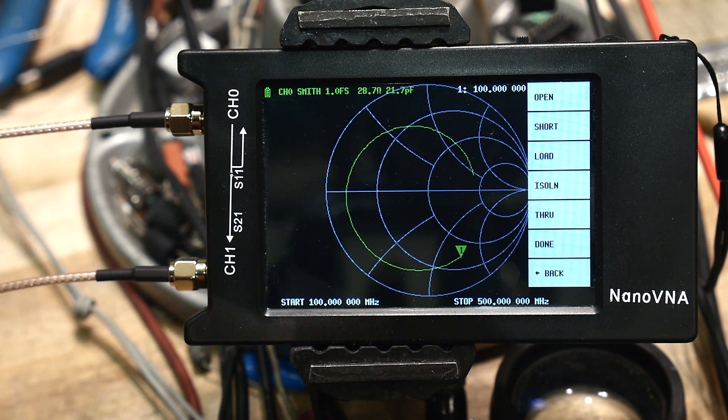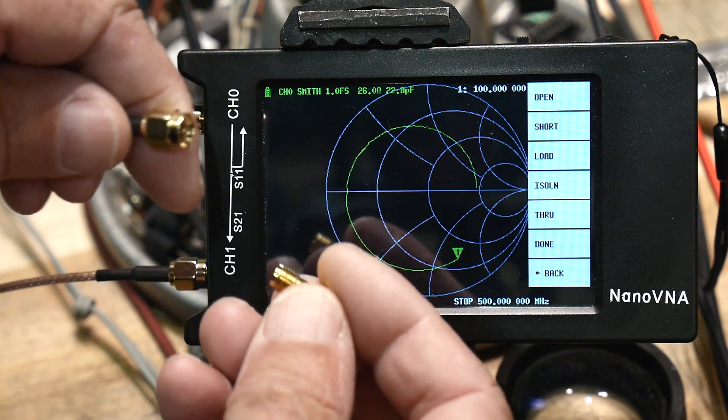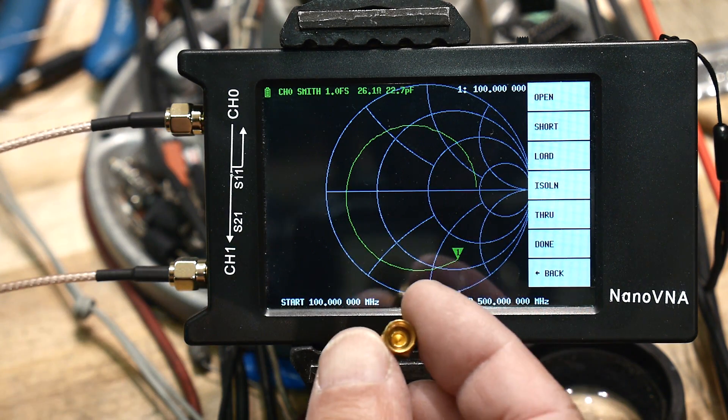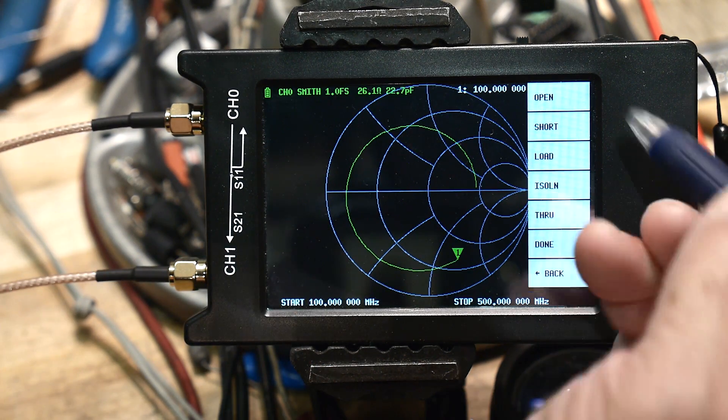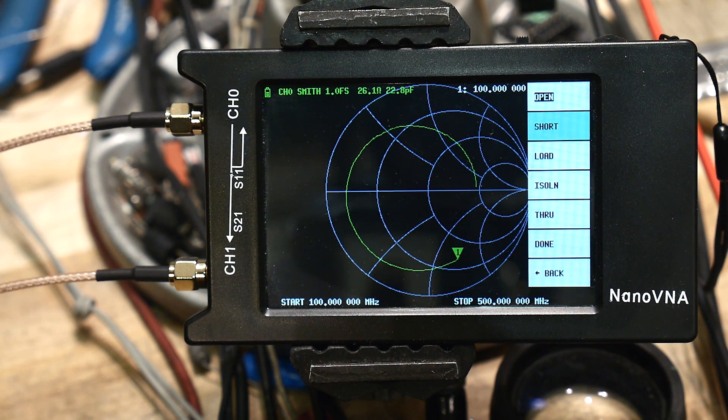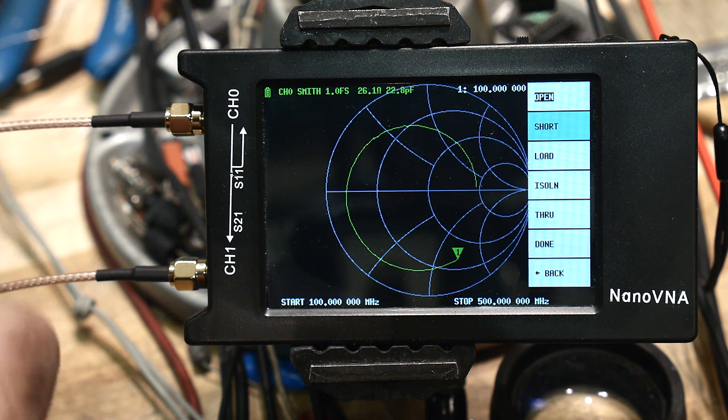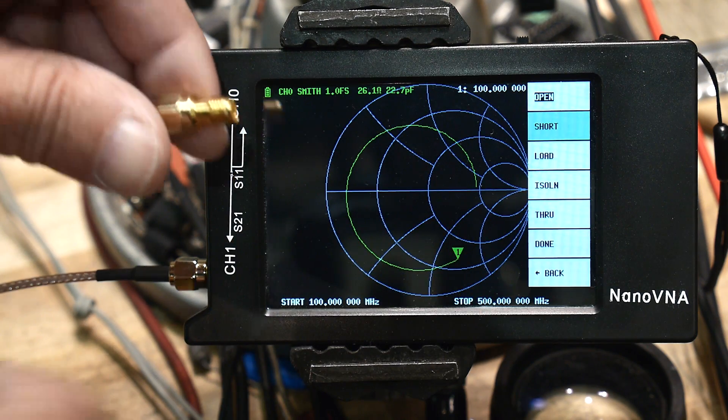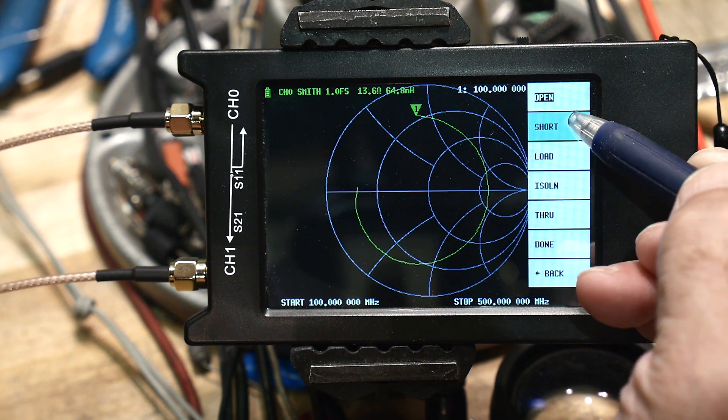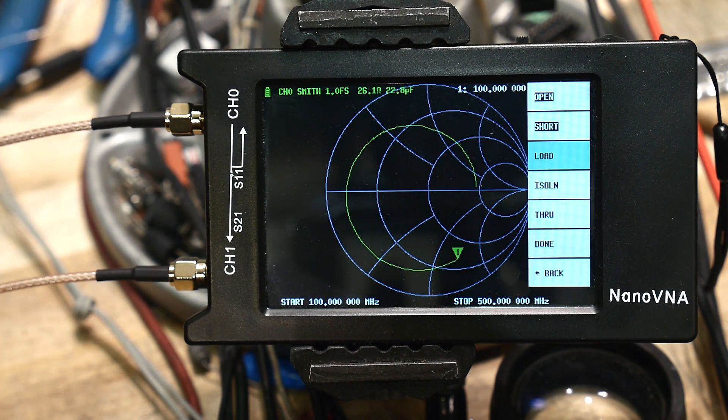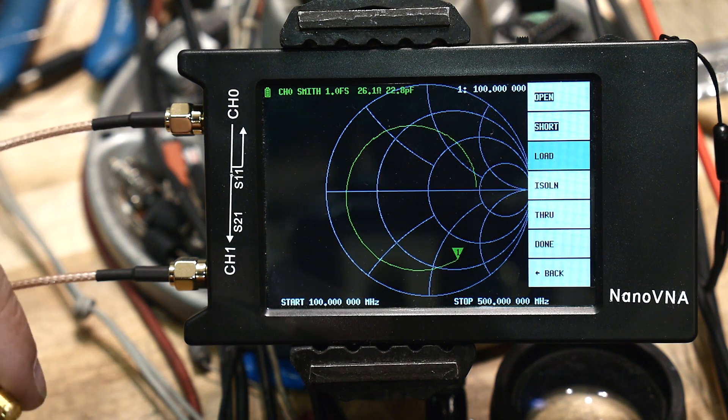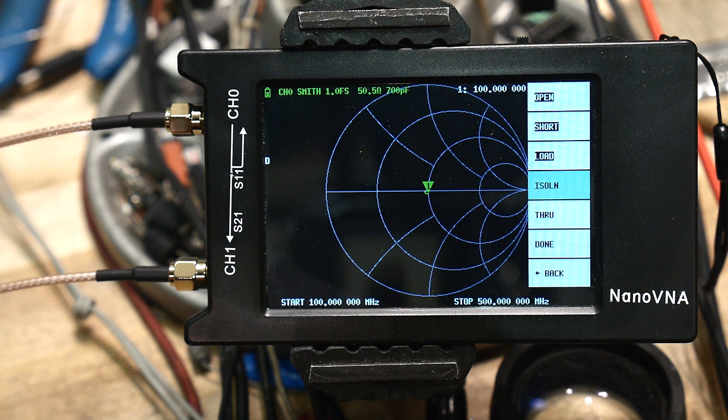Okay, so we're going to use what's supplied. First thing we need to do is an open. We're going to use the little through connector that's supplied, we'll put that on there first. And then we're going to go find our open. So here's our open, remember the O is the open. And we'll put that on here and then we'll press open. And we'll find the short, shiny one. Alright, I'll take that one off, put on the short, and we'll click on short.